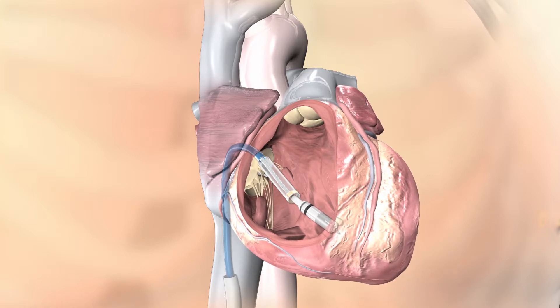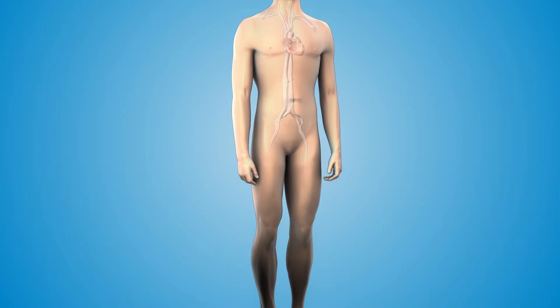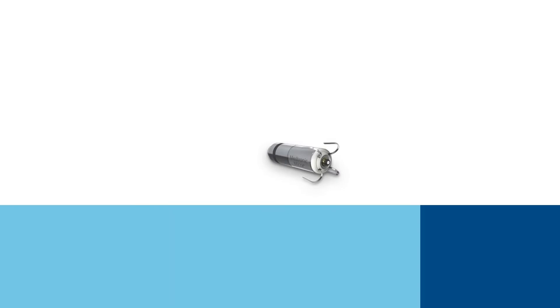The Micra Transcatheter Pacing System does not require a surgical incision or the creation of a pocket under the skin, which eliminates any visible sign of the device and a potential source of complications.